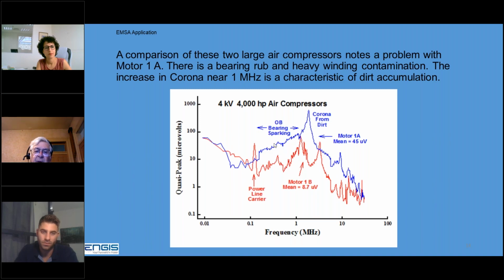Also, we had some sparking, which was a different pattern, and with a sniffer, we could tell it was the outboard bearing. So this motor really needs to be removed from service, cleaned, and the bearing repaired.